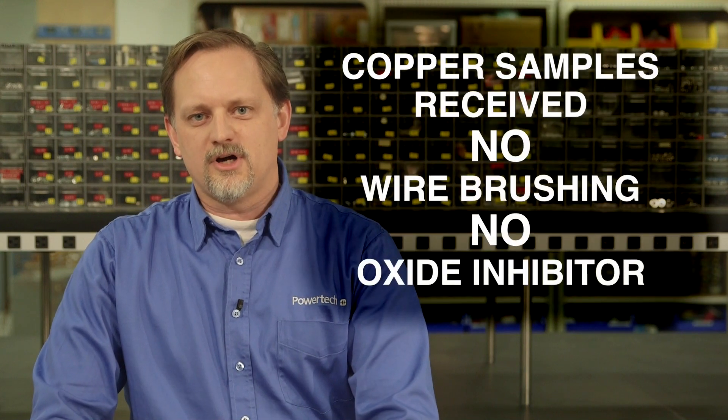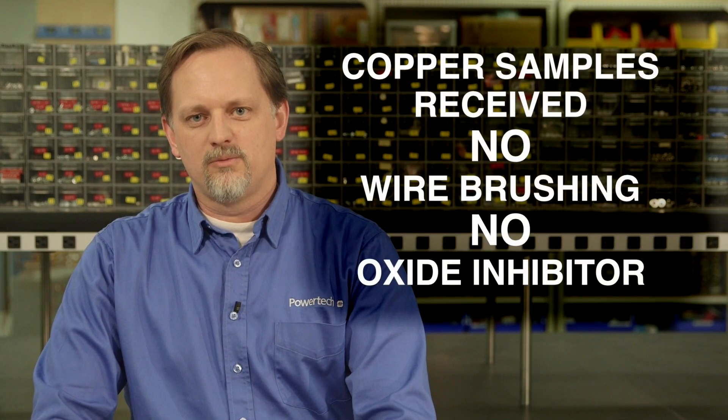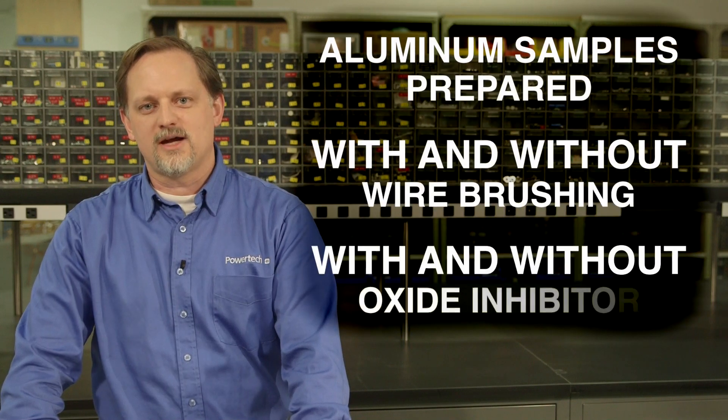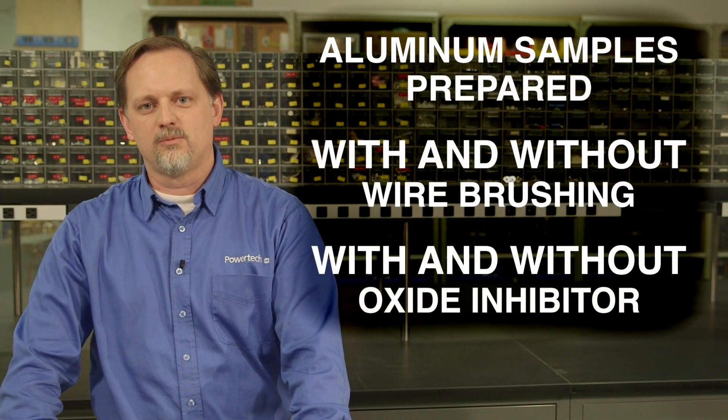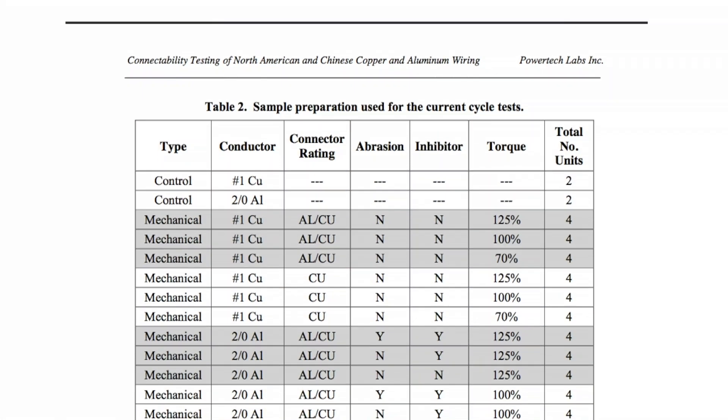Connectors were installed on copper wire samples with no wire brushing and no oxide inhibitor. Aluminum wire samples were installed with and without wire brushing, also with and without oxide inhibitor. This table shows a summary of the sample types and preparation methods.